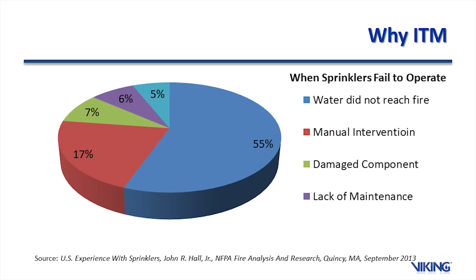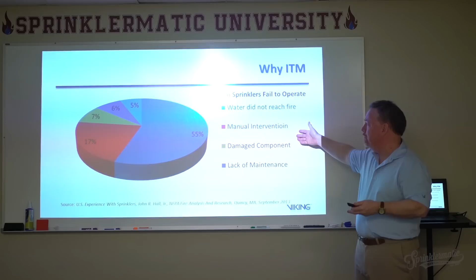Because in that 55% of the time when sprinklers failed to operate, water didn't even reach the fire. If the sprinklers failed to operate and water didn't reach the fire, that's typically a closed valve — so keep your valves open, which accounts for 55% of the time.